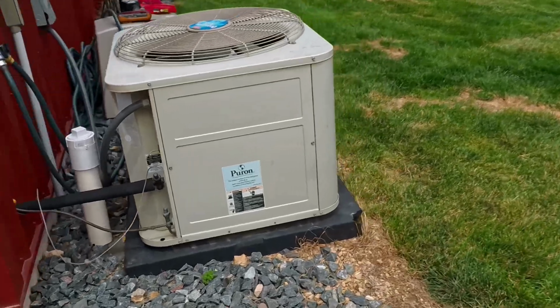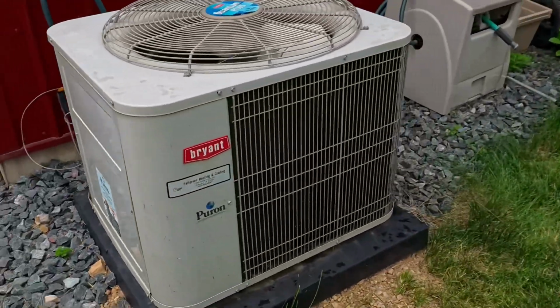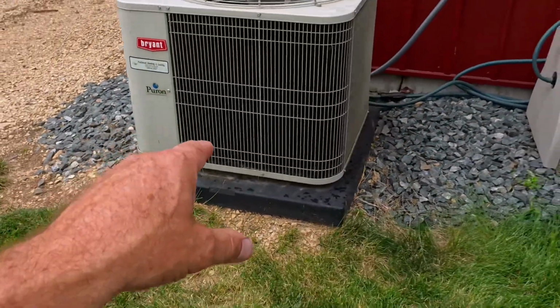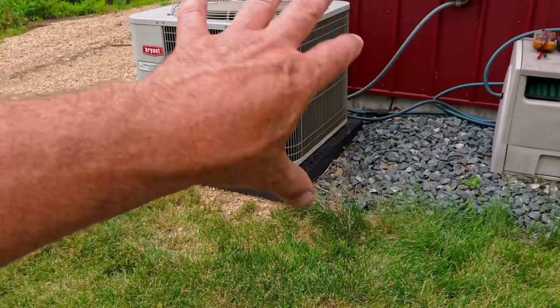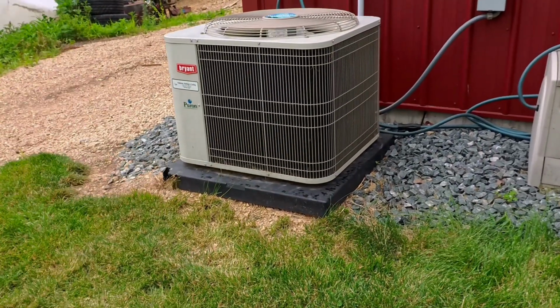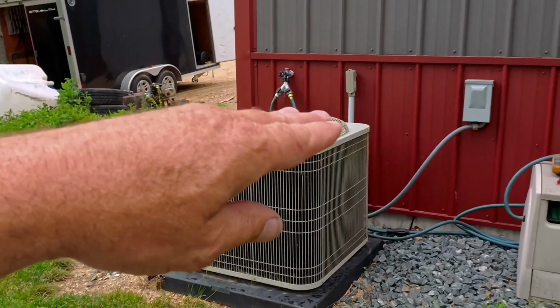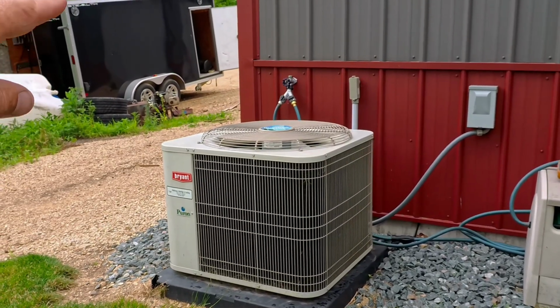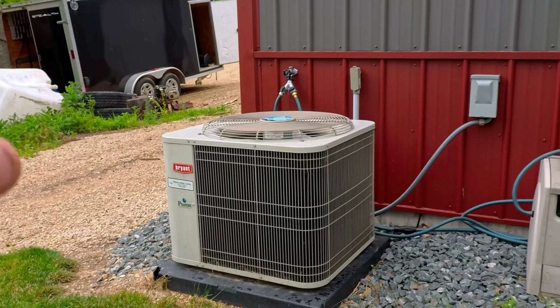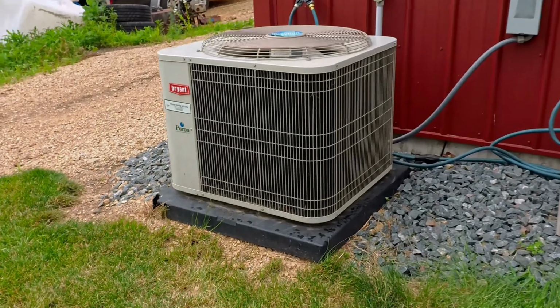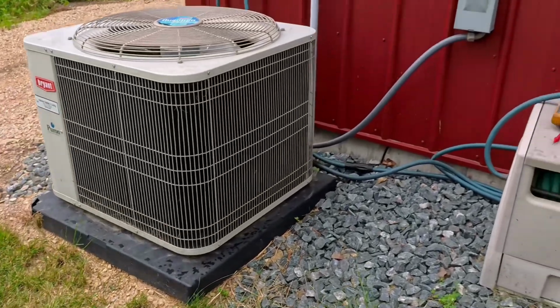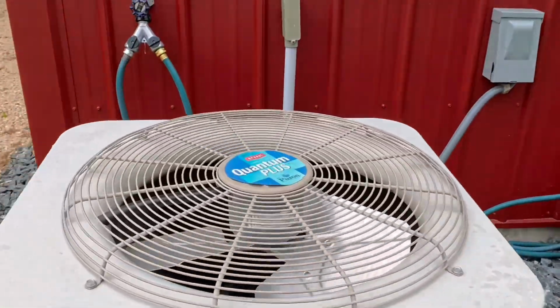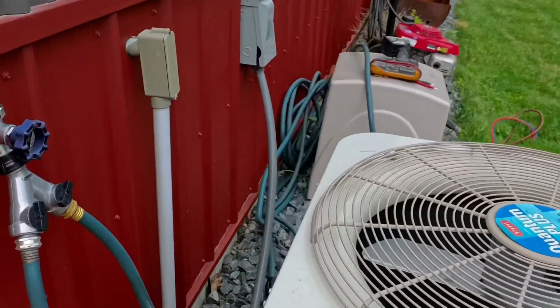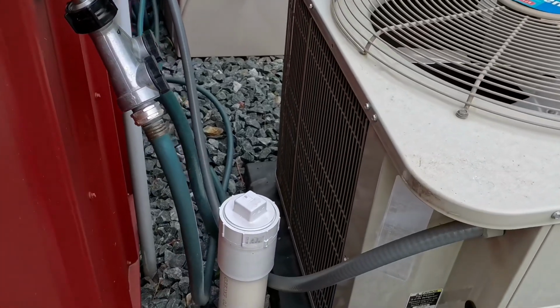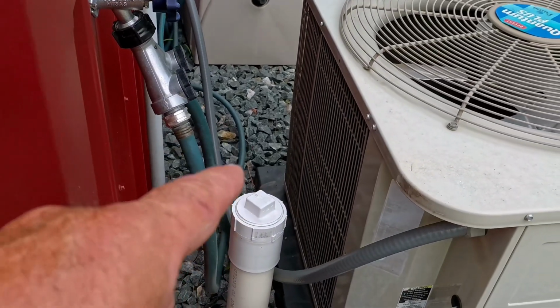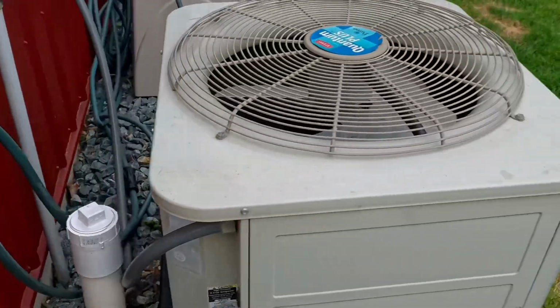And the other most important thing you can do to keep your system running well is to take care of this unit out here. Make sure there's no vegetation growing around it. Make sure the bushes aren't growing up against it. Make sure you didn't build a deck directly over top of it, because I've already seen that. Don't do that. This thing needs airflow, and it needs airflow on all sides. That's why it's placed a distance away from the building. And the other place that this thing is going to get dirty is between the building and the unit. That's the coil that will most likely get dirty first.